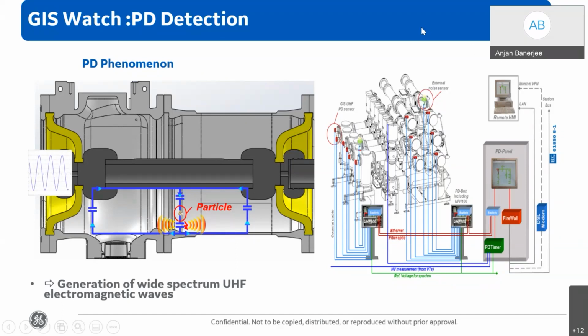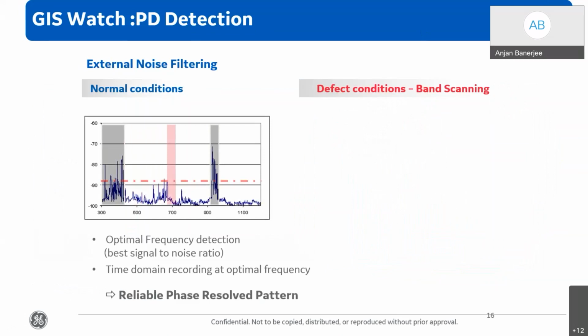These ultra high frequency antennas are connected to the intelligent electronic devices which acquire this UHF signal, do the analysis, and determine whether it is a genuine partial discharge event or noise. There is a robust algorithm available within the system to discriminate between an ultra high frequency signal originated due to noise and one generated due to partial discharge. As we can see over here, there is a narrowband frequency spectrum analysis available in the system. This system is always commissioned before the GIS is energized. Why do we do that? Because at that point of time, there would be noise in the environment, which would be captured by the external antenna located in the GIS. The system will capture these signals, and those signals would be masked, like those are the frequencies which are attached to noise.